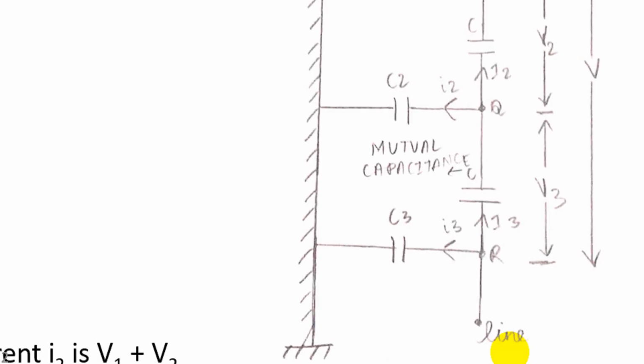So let's move on to the problems associated with the insulator. Let us take the first problem. The given question is: each line of a three-phase system is suspended by a string of three similar insulators. If the voltage across the line unit is 20 kV, calculate the line to neutral voltage and string efficiency. Assume the shunt capacitance of each link to be 1/10th of the capacitance of the insulator.